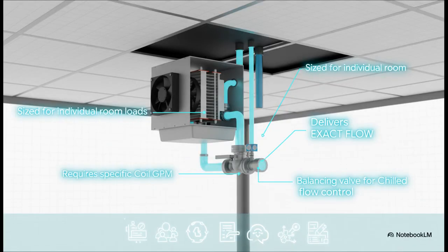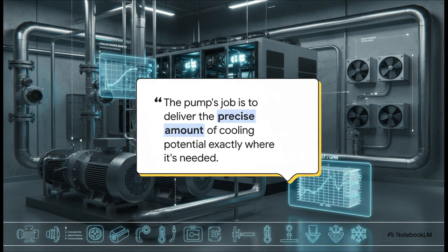And for smaller, individual rooms or zones, we use these little guys, fan coil units, or FCUs. They work on the exact same principle, just on a much smaller scale. Each one needs a very specific GPM to handle its room's cooling load, and we use little balancing valves to make sure every single FCU gets the exact flow it needs, no more, no less. You know, there's a quote that I think just perfectly captures the elegance of this whole design. A chilled water pump isn't just some brute force machine. It's a precision instrument. Its entire purpose is to deliver energy in the form of cold water to the exact spots that need it, at the exact rate they need it.